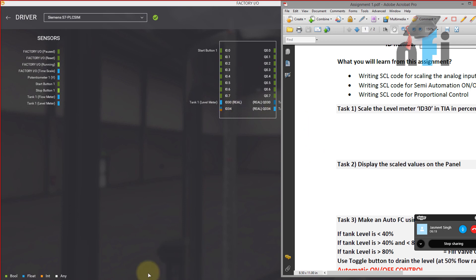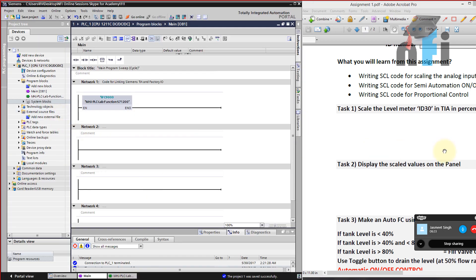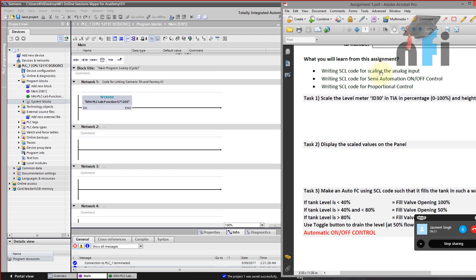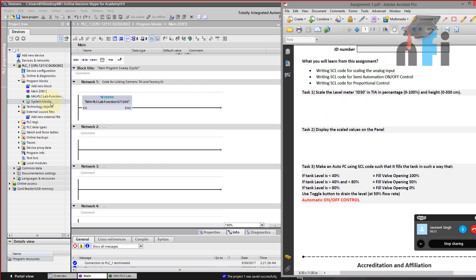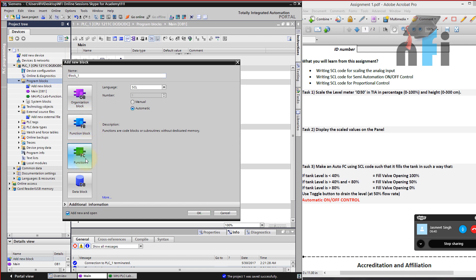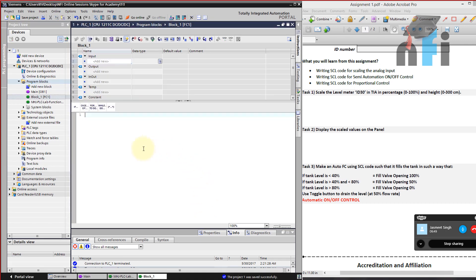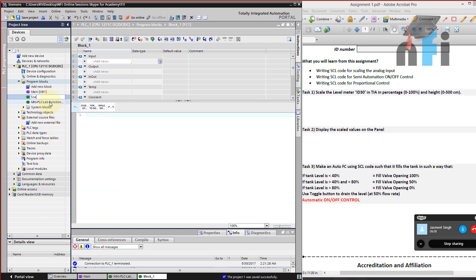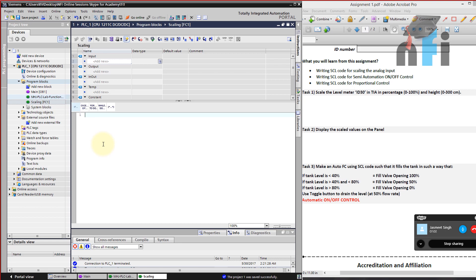We have to scale the value of ID 30, which is the level meter, so we'll go back to our PLC and write this in SCL — a widely-used programming language in Siemens. In the program block, click 'Add new block', go to Functions, and select SCL language. Once you click OK, you will find the function window. We can rename this block as 'scaling' because here we are going to create our own function to scale the value to 100%. Our ID 30 gets a value of 0 to 10 and we need to scale it to 0 to 100%.